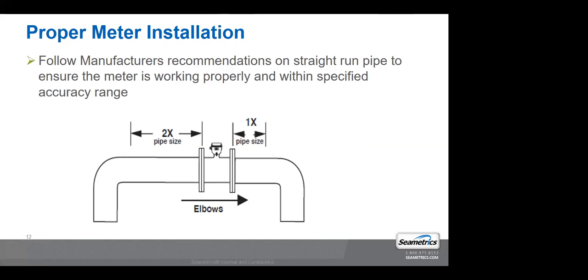So on full bore mag meters, your typical requirement is 2 pipe diameters upstream. What that means is you take your pipe size, if it's a 10-inch pipe, you multiply it by 2. So you'd want 20 inches of straight run pipe before the meter. Whether it's a pump, an elbow, a half open valve, whatever it is, a chemigation valve, you'd want 20 inches. Then on the downstream side, you'd want 1 pipe diameter, which is 10 inches. That's an ideal installation, and that is accounting for any type of variable you could have on either side.